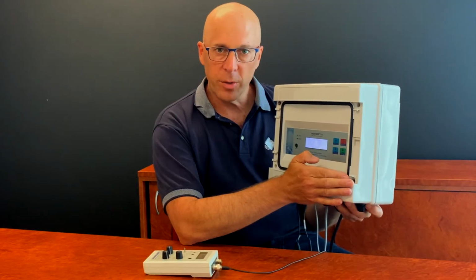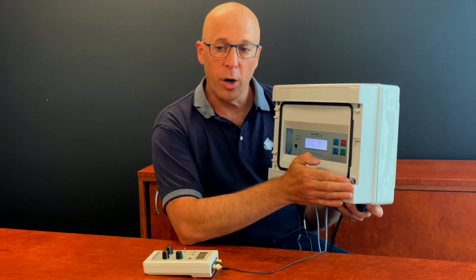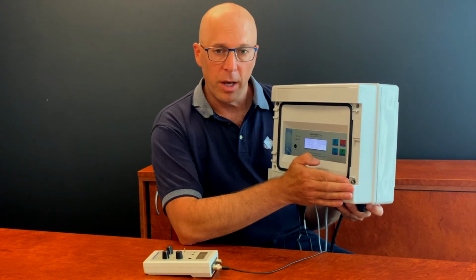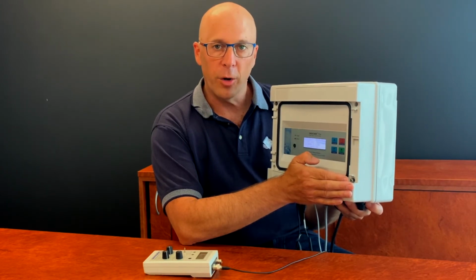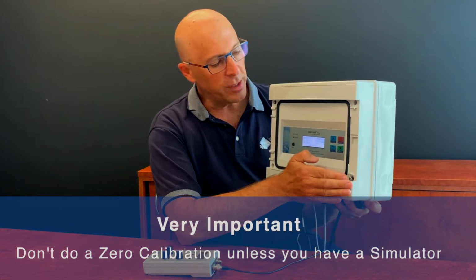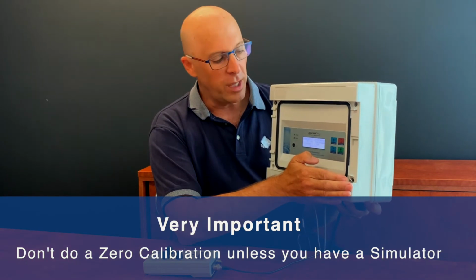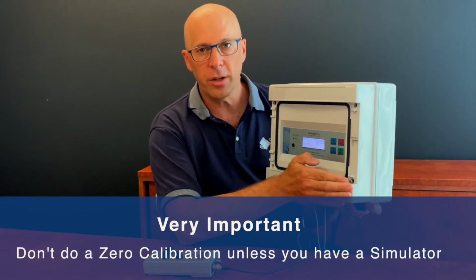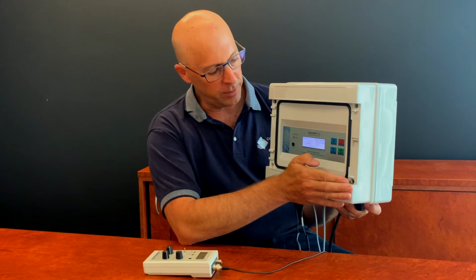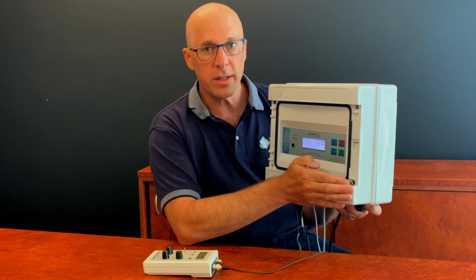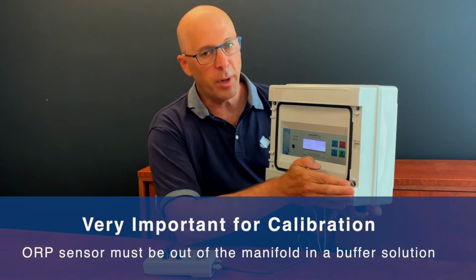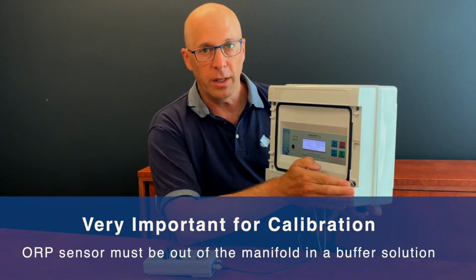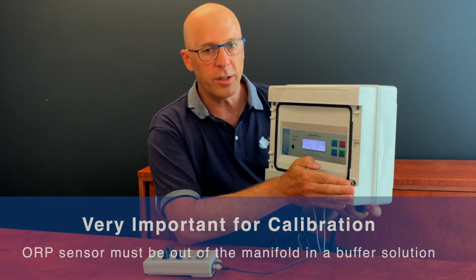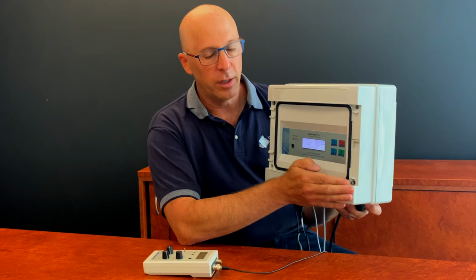It is also possible to use an ORP buffer solution and have the ORP probe in that solution when we're calibrating the slope, but it's very important that you don't do a 0 calibration unless you have a simulator in order to do it. Another important caution is that the ORP sensor must be out of the manifold in a buffer solution in order to calibrate it. You cannot calibrate the controller having the ORP probe in the manifold with all the other sensors.